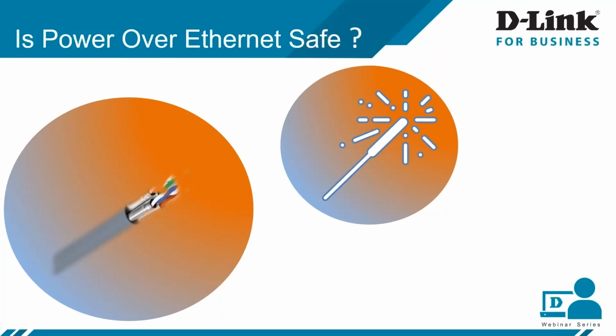That is the reason the NEC specifies or revises the code when we are talking about Type 3 and Type 4. So what does the NEC do? The NEC specifies how many cables should be allowed in a bundle, and this depends on your conductor size and the temperature rating. For 60 watt and higher PoE, you are required to use limited power cable.